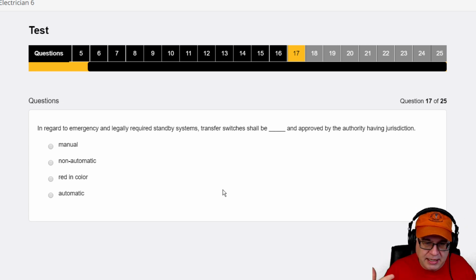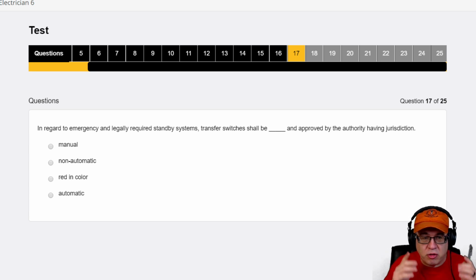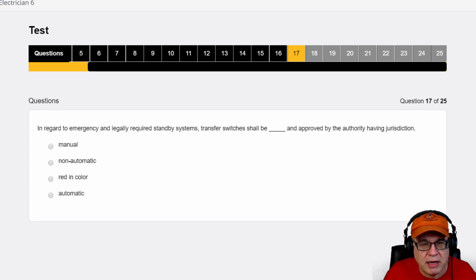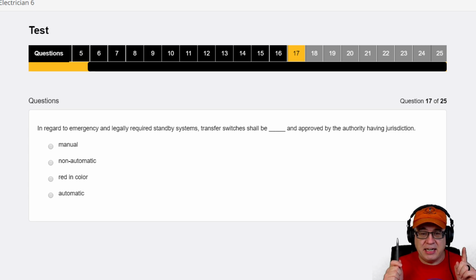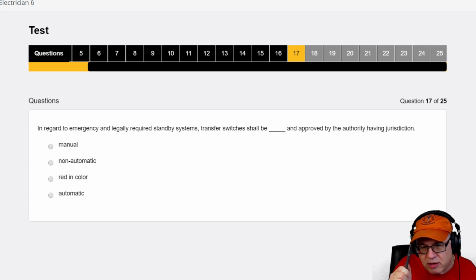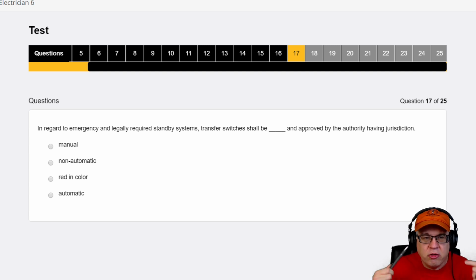But if we had to find it, we'd look for the keywords. We're dealing with emergency and legally required, so the reference should be identical in 700 and 701. We're also dealing with transfer switches, so that's identical too. The one thing to remember is that 'authority having jurisdiction' is pretty unique, so that's a trigger to look for once I get to where I need to be.